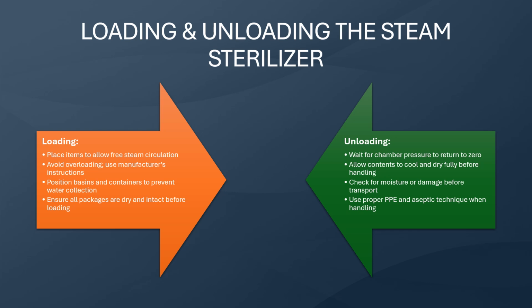Proper loading and unloading of the steam sterilizer is crucial to ensure effective sterilization and to maintain the sterility of the items being processed. So during the loading portion of it, when you're on the sterilization portion of your facility, you're in charge of how that autoclave rack is being loaded up. So it's essential to arrange those packages so that steam can circulate freely, preventing any air pockets and ensuring the uniform sterilization. Items must be spaced correctly and not stacked tightly. So when you have peel packs, don't put a lot of peel packs to where they're packed in tightly.